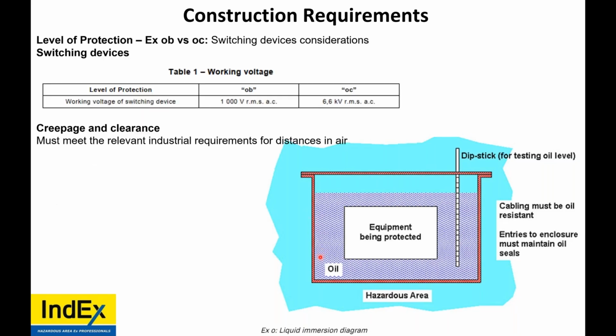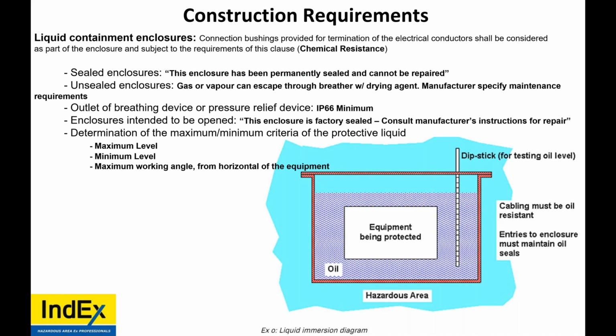So when we go to levels of protection, we have Ex ob or oc, so for zone 1 or zone 2, or EPL GB or GC. Well, for OB, our switching devices have to have a working voltage of 1000 volts RMS VAC, while in Ex oc, they can be up to 6.6 kilovolts. Now, creepage and clearance distances must meet the relevant industrial requirement for distances in air. So if we ask a question in a moment.